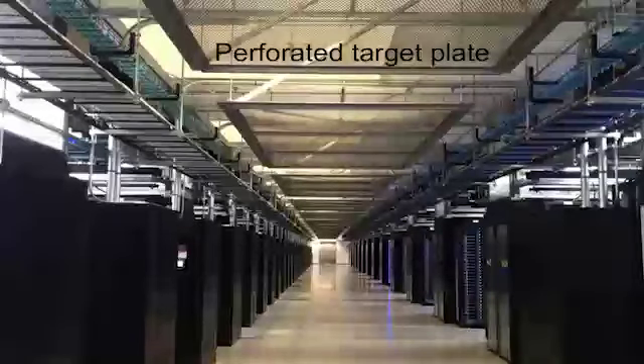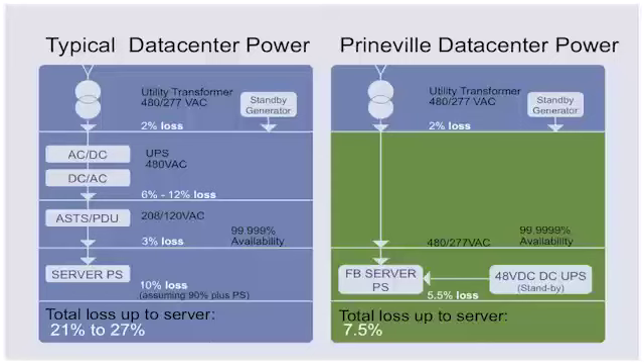Our electrical distribution. In a traditional data center, you'll take your 480, 277, go through a dual conversion mode, and then ultimately feed 208 to your servers. What we've done is eliminate the necessity of that traditional UPS system, designing our servers with power supplies that can take the 277 volt, coupled with 48 volt input from our DC UPS that are located out on the floor. By taking control of the server design and the power supplies, we were able to utilize power supplies that are very efficient. On a typical electrical distribution scheme, you might have 21% to 27% losses. In our design, we're at 7.5, so about a 13% delta.